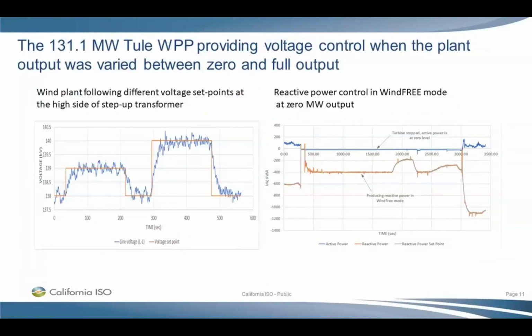This plot shows you how well a wind plant could provide voltage control. Again, the voltage set points are the bars, and the blue wiggly curve is how well this wind plant was able to follow a voltage set point. You lower the voltage, you increase the voltage slightly, and the wind plant was able to follow that signal accurately. The one I like is the plot to the right. That plant could produce reactive power at 0 megawatt output. So that blue line is no megawatt output. During any time of the day with no active power output, this wind plant could control voltage.